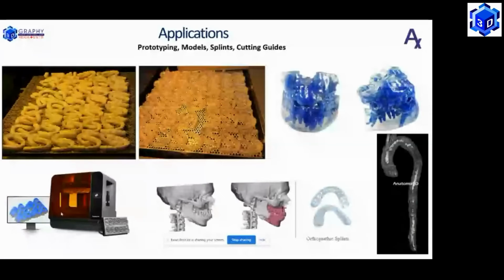Basis this simulation, since it's a two-stage simulation, there are two splints, that is one to set the mandibular advancement and then the other splint to set the final occlusion position. These splints are provided so that the simulation that we do on the software is exactly mimicked onto the patient, giving the best possible occlusion and aesthetic output.